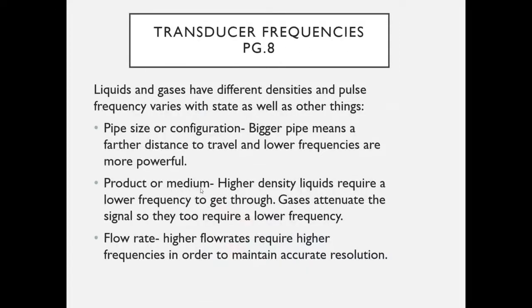There is science behind the transducers we need to understand for proper application and installation. Liquids and gases have different densities, and the pulse frequency varies with the process medium. Higher or lower densities affect sound waves differently. Pipe size also matters — a bigger pipe means a farther distance to travel, so we want lower frequency transmissions from our transducers, because lower frequencies are inherently more powerful.